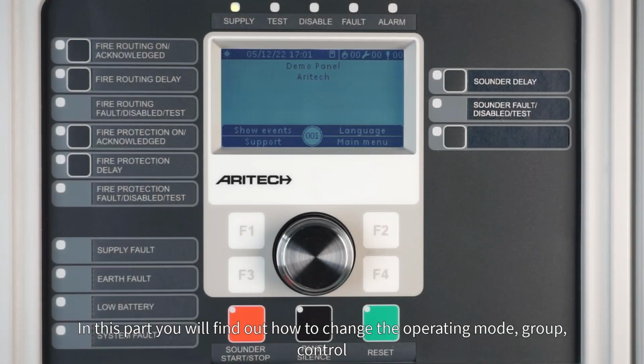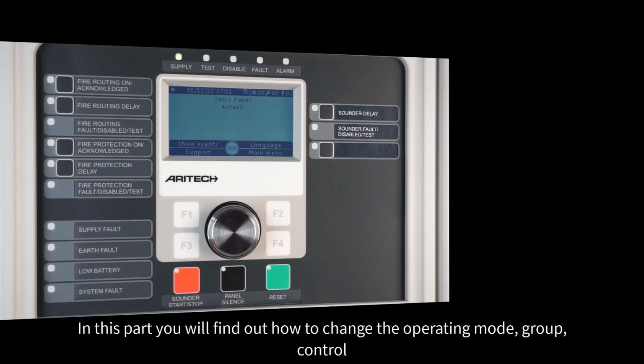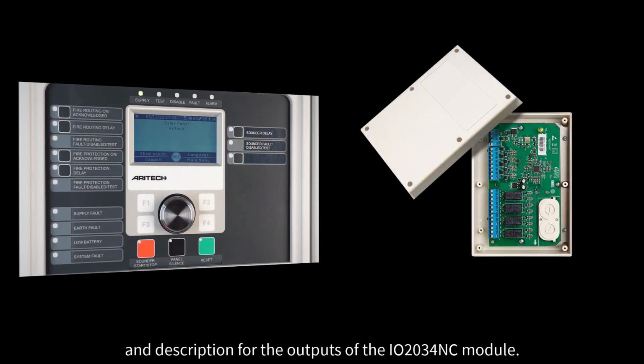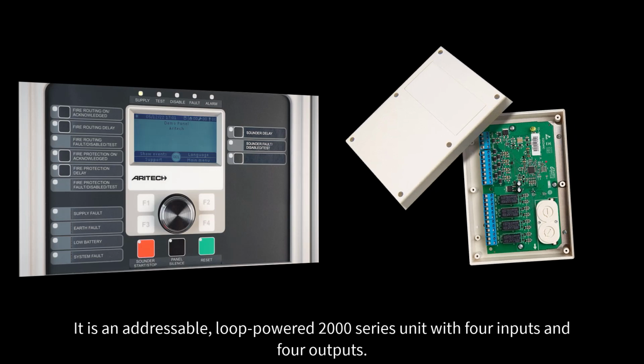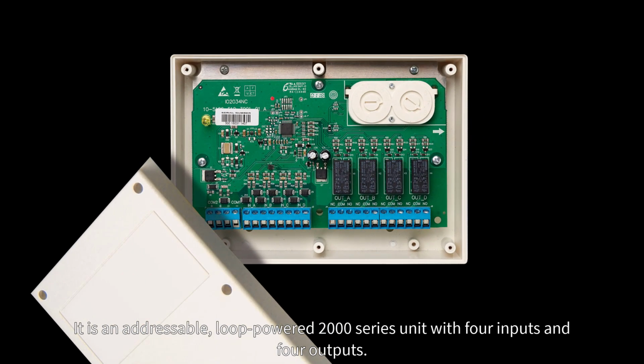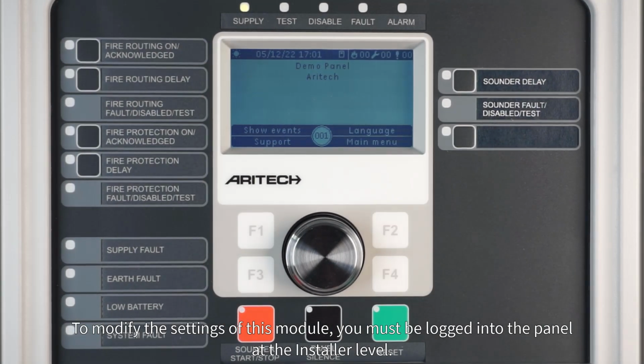In this part you will find out how to change the operating mode, group, control and description for the outputs of the IO2034NC module. It is an addressable, loop-powered 2000 series unit, with 4 inputs and 4 outputs. To modify the settings of this module, you must be logged into the panel at the installer level.